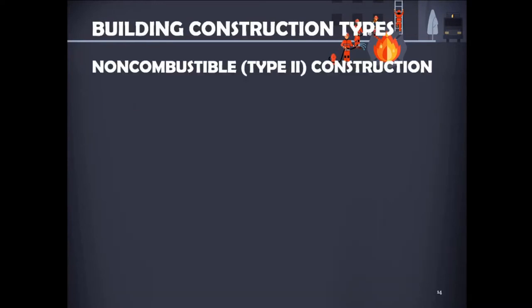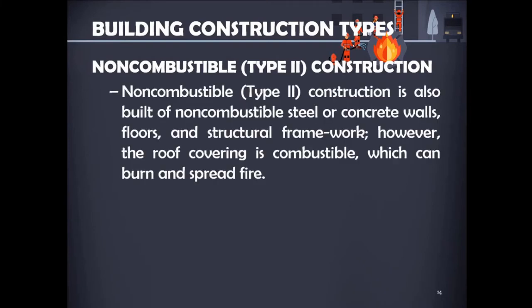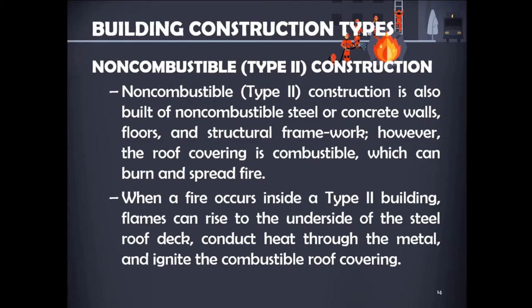Second is non-combustible Type 2 construction, also built of non-combustible steel or concrete walls, floors, and structural framework. However, the roof covering is combustible and can burn and spread fire. The roof covering of a Type 2 building can be constructed of a combustible built-up roof covering, a layered asphalt and felt paper covering, or an ethylene-propylene-diene monomer (EPDM) or polyvinyl chloride (PVC) thermoplastic membrane. When a fire occurs inside a Type 2 building, flames can rise to the underside of the steel roof deck, conduct heat through metal, and ignite the combustible roof covering. The asphalt, felt paper, and foam insulation may burn and spread fire along the roof covering.